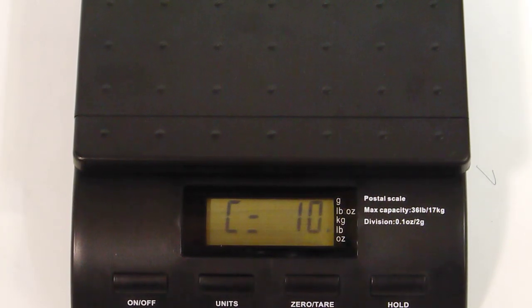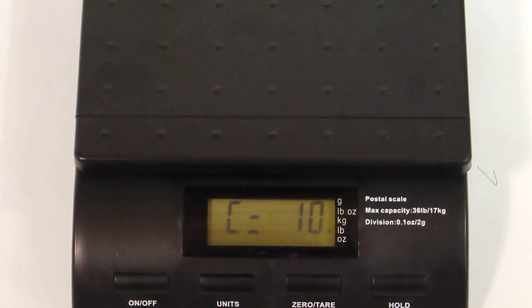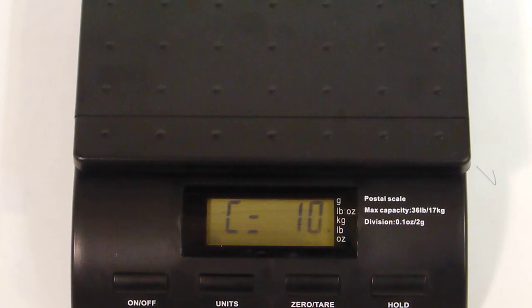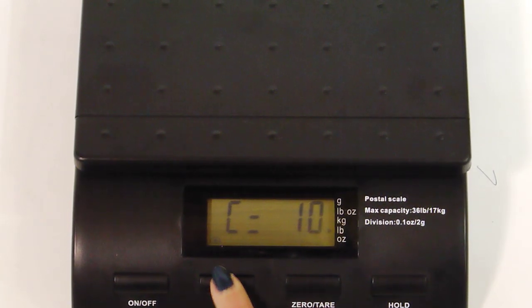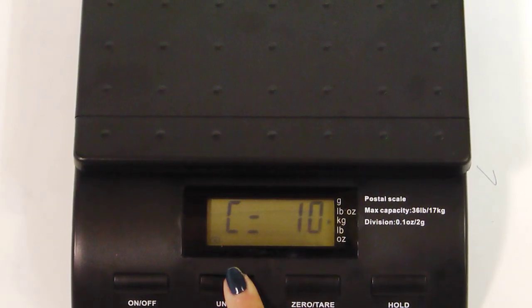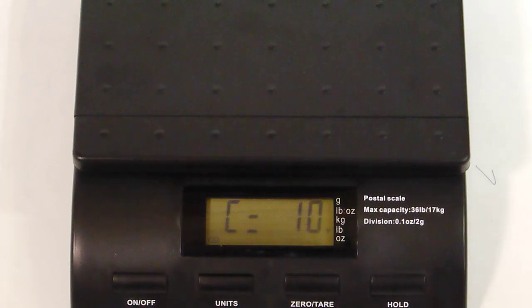Release both keys and you can see C equals the calibration weight. Press the unit key to choose the calibration weight. Today we're going to use 10 pounds.